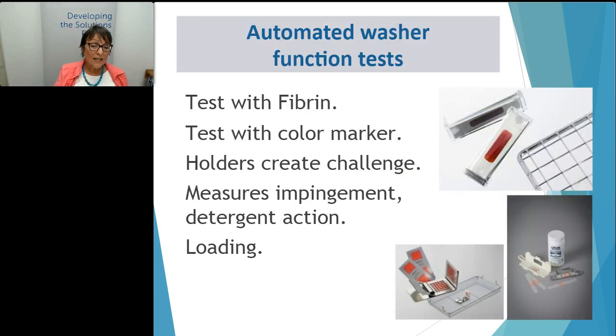Likewise with washer tests. They don't guarantee that your instruments are clean. What they are helping you do is figure out if your cleaning device, your washer, is actually working. I'm personally a fan of TOSI type tests that have fibrin as well as a color marker because they're more resistant, and they are really the true, what I would call gold standard for figuring out if your washer is working. There are other types and other brands of these colored dyes with various types of holders, and they measure both impingement and detergent action. Again, we see a product that also measures enzymatic activity.